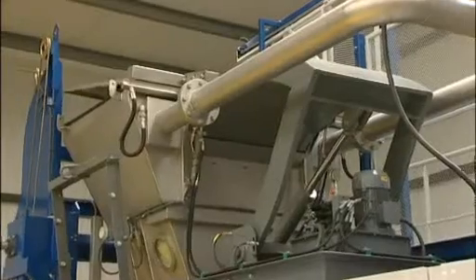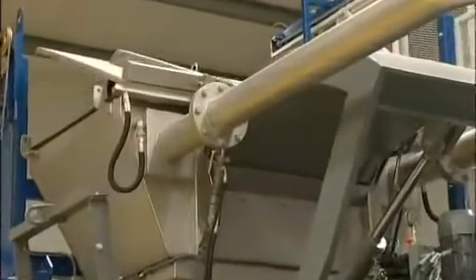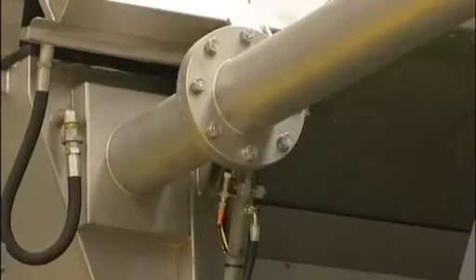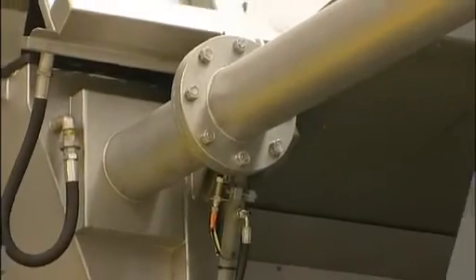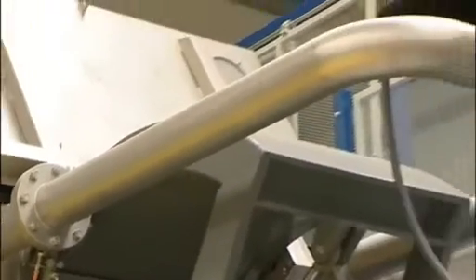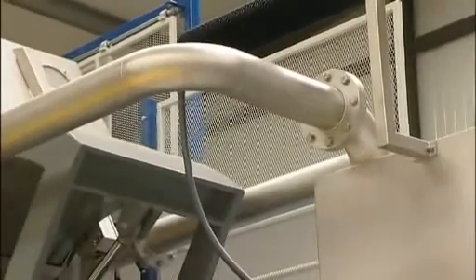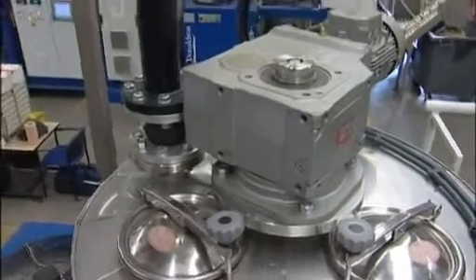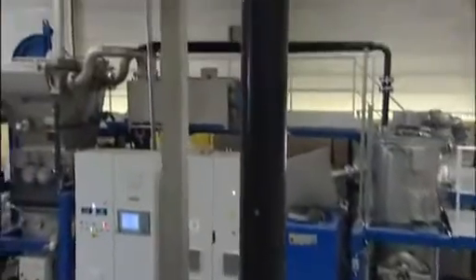The loading hopper has an air treatment vessel that creates a vacuum when it opens, preventing dust from being whirled up when opening the hopper. The airflow is washed, disinfected, deodorized, and filtrated over activated charcoal. The airflow is rejected outside only after this treatment.